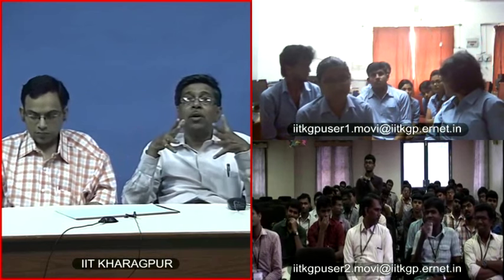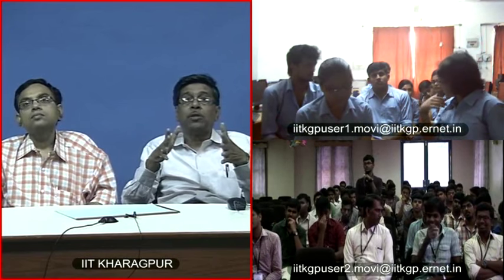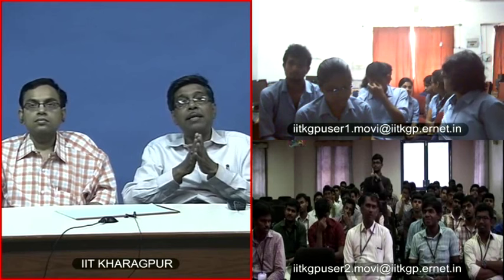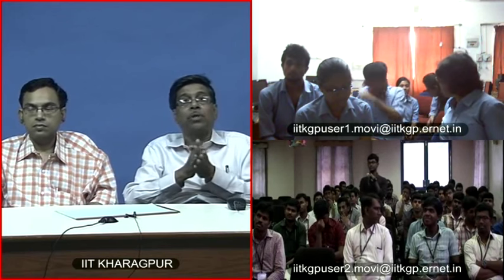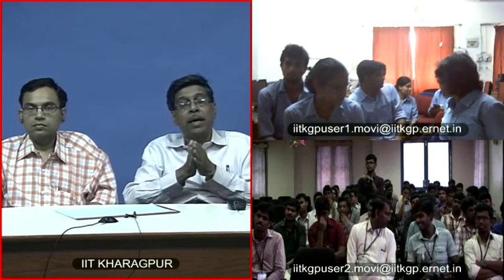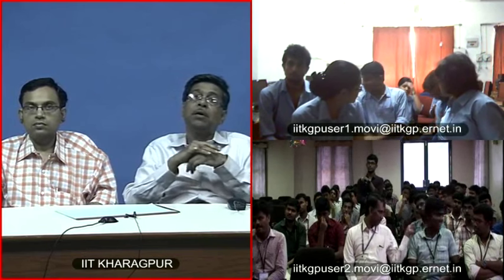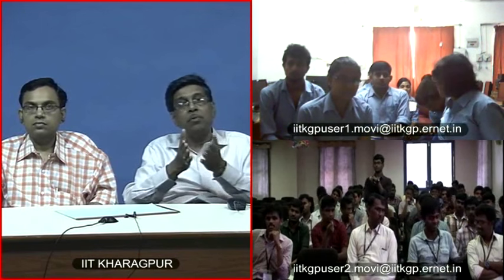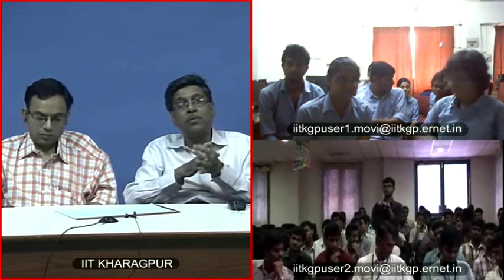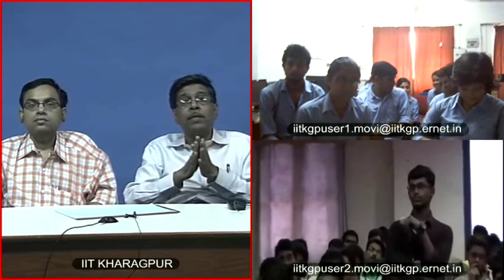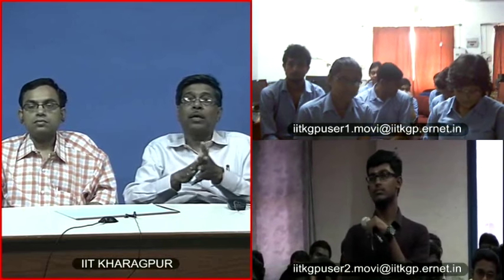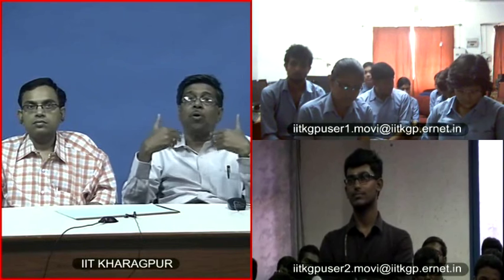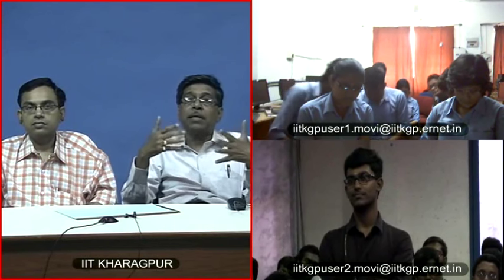That means there are different flow geometries for the two fluids to flow through, and they are separated by a solid boundary, and heat is transferred from one fluid to the other, from the fluid which is relatively at high temperature to the fluid which is relatively at cold temperature. The partition wall also acts as a thermal barrier, but it is usually of very high thermal conductivity and very small thickness. The sole objective is to transfer heat from one fluid to the other fluid. So the atmosphere is not allowed to take part in it. So the heat exchanger is always insulated so that transfer takes place only between the two fluids.